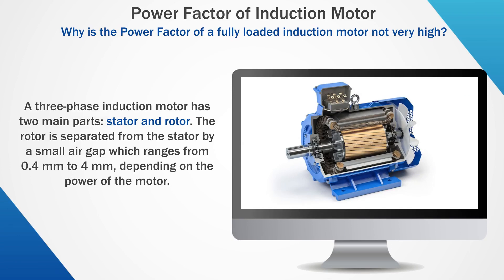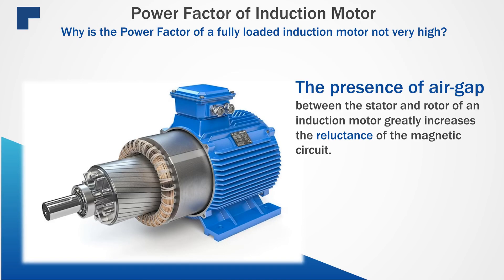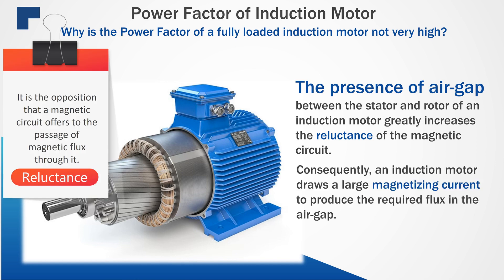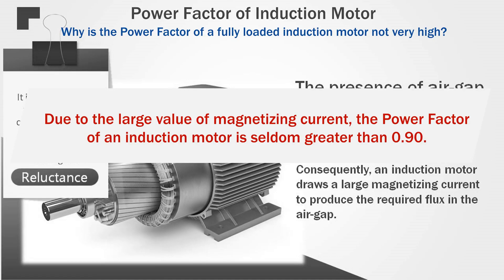A three-phase induction motor has two main parts: stator and rotor. The rotor is separated from the stator by a small air gap, which ranges from 0.4 mm to 4 mm depending on the power of the motor. The presence of the air gap between the stator and rotor greatly increases the reluctance of the magnetic circuit. As a result, an induction motor draws a large magnetizing current to produce the required flux in the air gap. Due to this, the power factor of an induction motor seldom exceeds 90%.